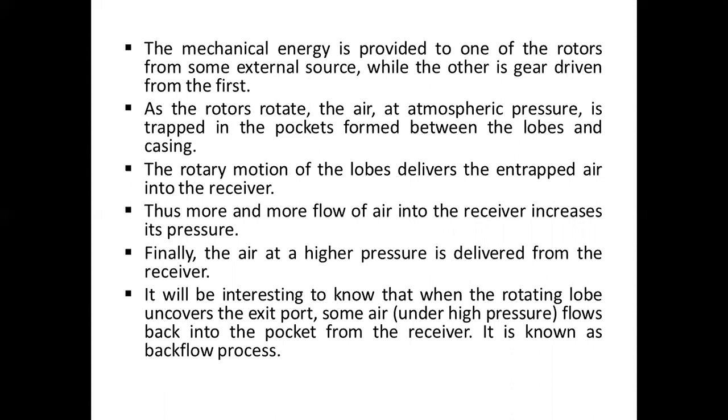When the rotating lobe uncovers the exit port, some air flows back into the pocket from the receiver. It is known as the backflow process. The air which flows from the receiver to the pocket gets mixed up with the entrapped air. The backflow of air continues till the pressure in the pocket and the receiver is equalized.